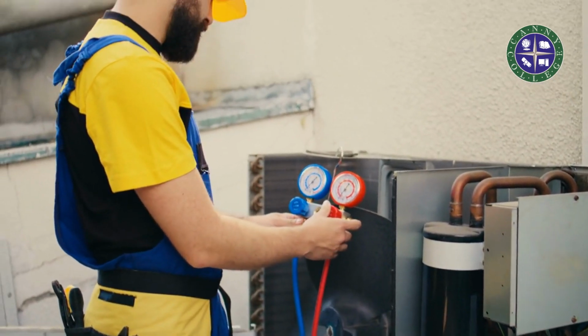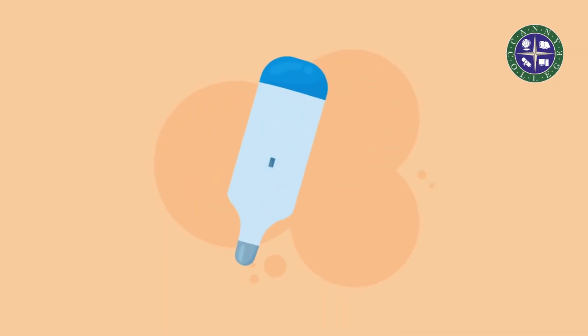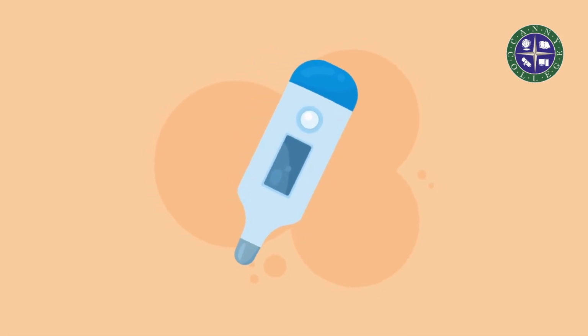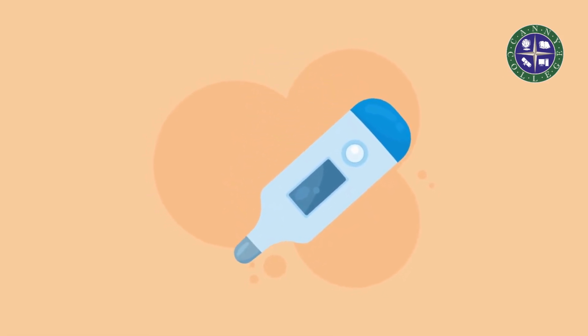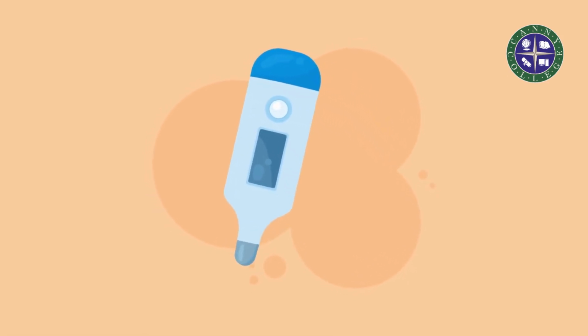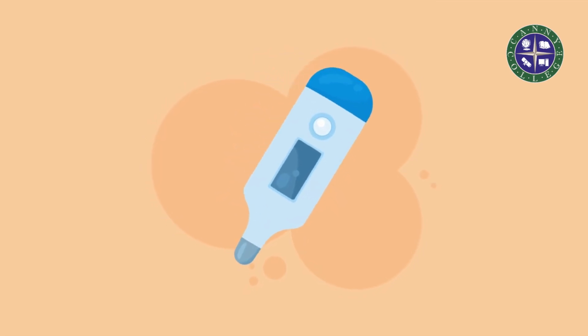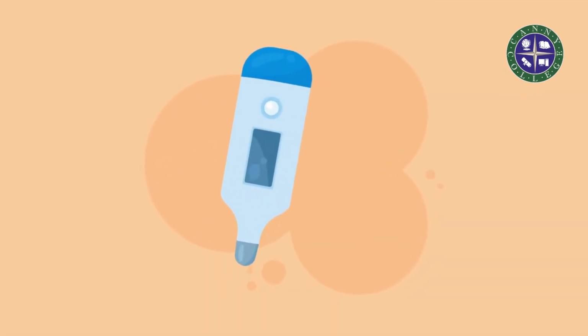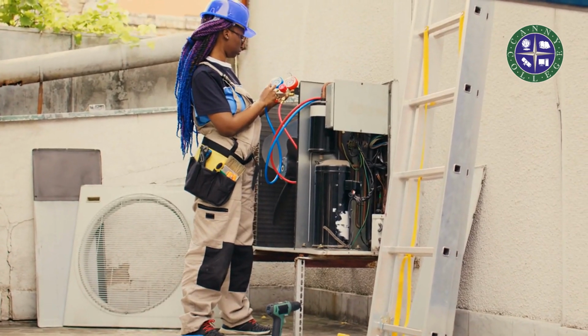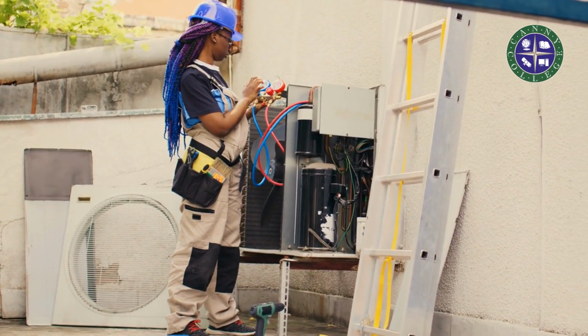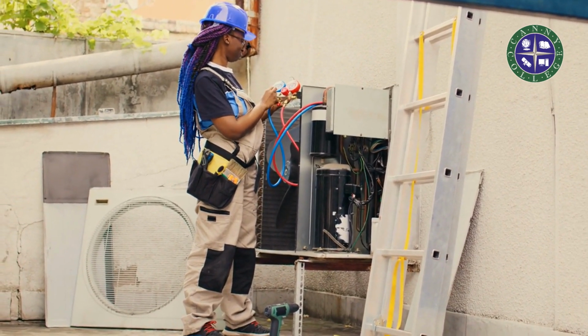4. These instruments, thermometer, psychrometer, and multimeter, provide comprehensive data on temperature, humidity, and electrical parameters necessary for calibrating the enthalpy control on the rooftop air conditioning unit's economizer. They enable accurate adjustment and optimization of the economizer's operation for efficient energy utilization.